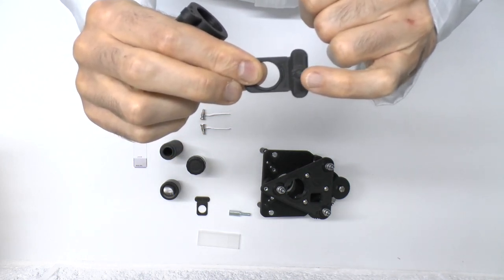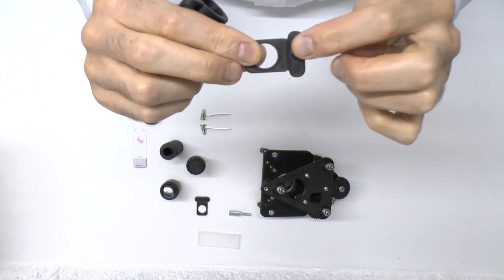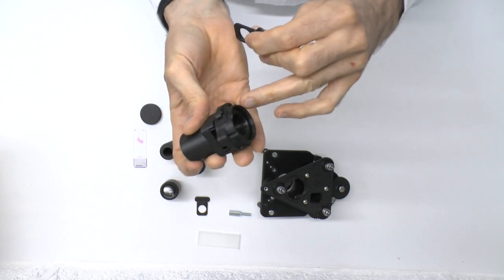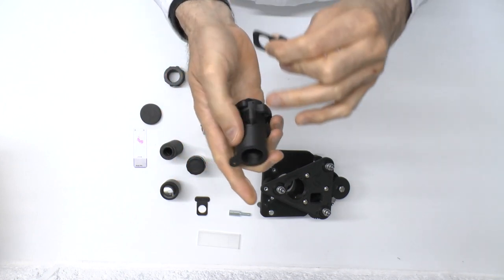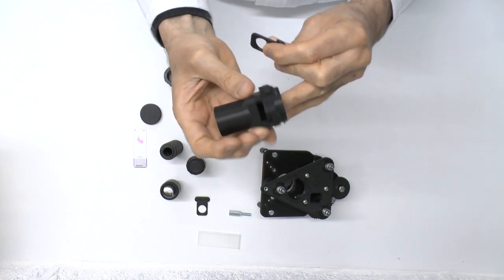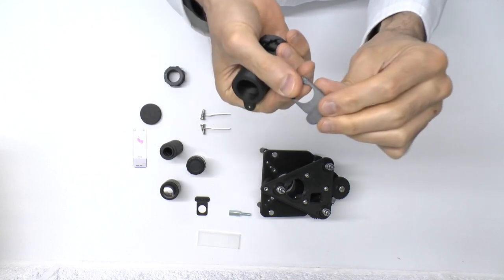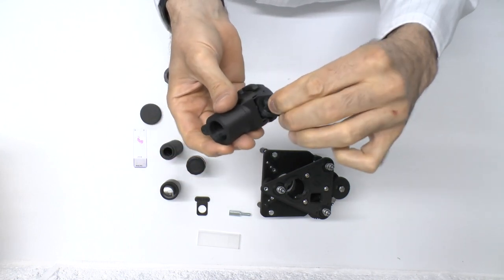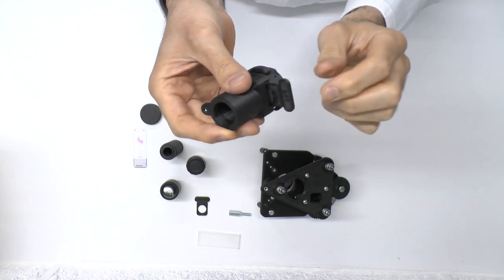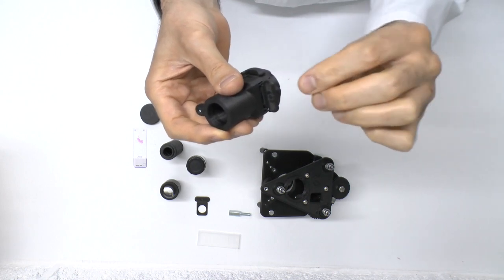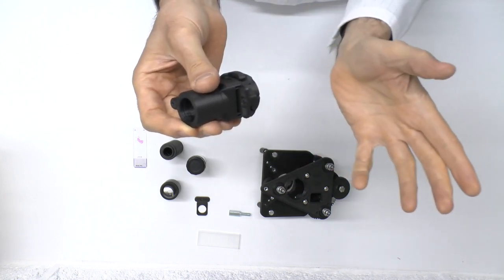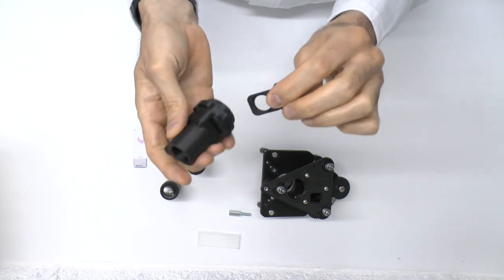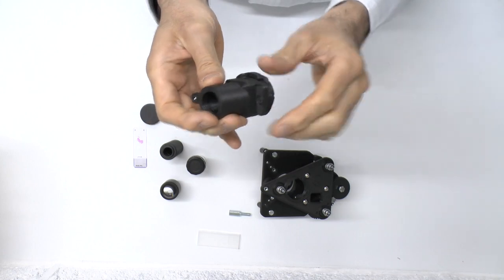You can see a little symbol on the slider here. That shows you that this is the top surface. Top surface means it goes towards this lug. That's the top surface. The bottom surface is the thread that the RMS objective goes into. So that's top. That's bottom. We've got the filter slots here. And we have this marking. There's no marking on the other side. So the one with the marking is top. So that has to go facing the top side. And you put the bottom filter in first, because then you can rest that on the quick release part here. That goes in. Be careful not to move it so it crosses up onto the upper slot. Clicks in place. And once that's in, it's relatively easy to put the other filter slot. Again, correct side facing up into the top slot and clicks in place. That's done.